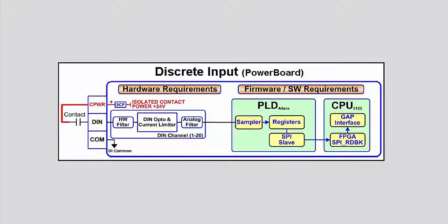In this case, terminal 24 contact input common must be connected to the external power sources common in order to establish a common reference point.